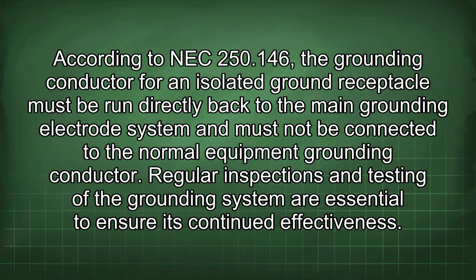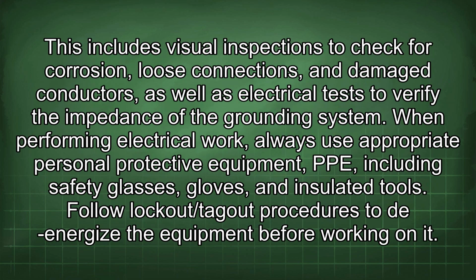Regular inspections and testing of the grounding system are essential to ensure its continued effectiveness. This includes visual inspections to check for corrosion, loose connections, and damaged conductors, as well as electrical tests to verify the impedance of the grounding system.